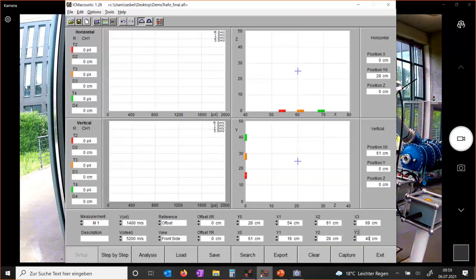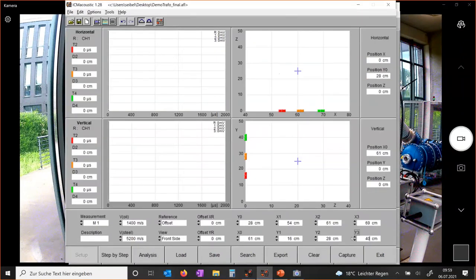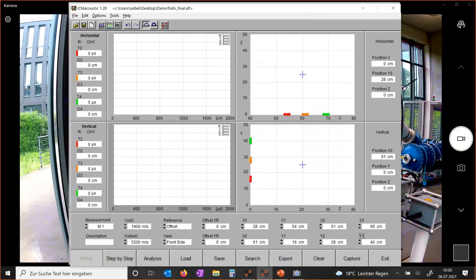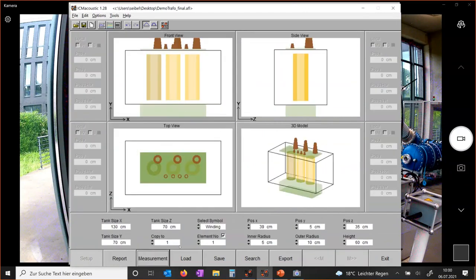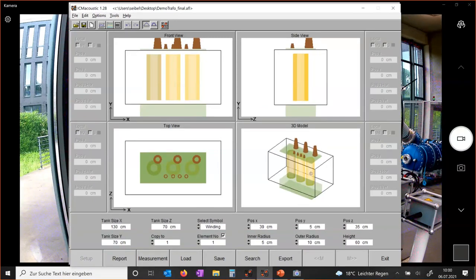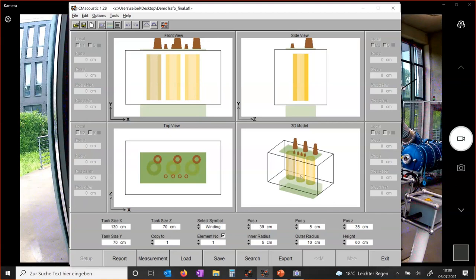This is the ICM acoustic software. I've started a new measurement and already entered the exact positions of the sensors we are using and will use after rearrangement. For further analysis, I created a 3D model of this transformer, and once the measurement is done, the software will show the exact location of the fault.